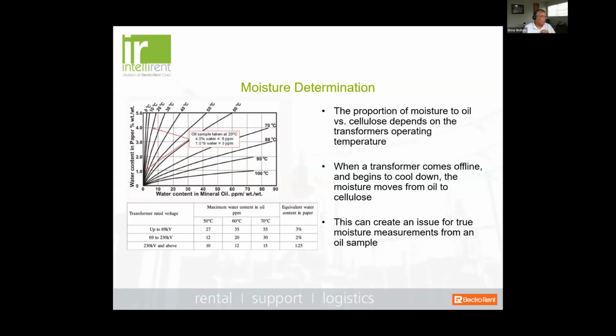So what IEEE tried to do was establish what they call equilibrium curves, and that is to try and use temperature correction to estimate what is actually percentages in the oil versus what's in the insulation. And it's the moisture in the insulation that, of course, we have the major concern with. So, think of this: oil samples can become contaminated from exposure to the outside air. That will influence it, and it doesn't take long for that to happen. Also, the way you take the sample has to be done very carefully. The temperature correction has to be measured very carefully. And think about this: what happens if you're going to measure the oil temperature?